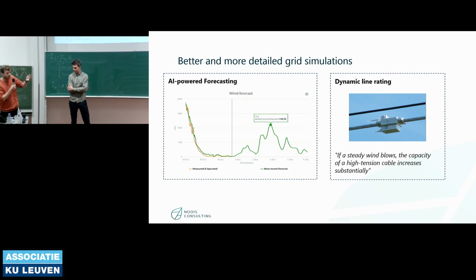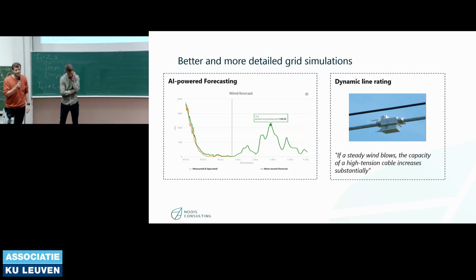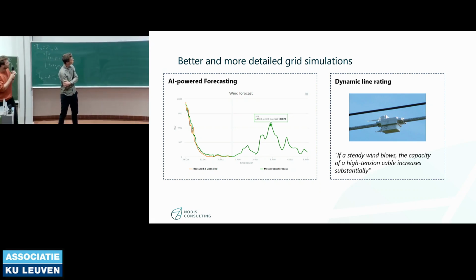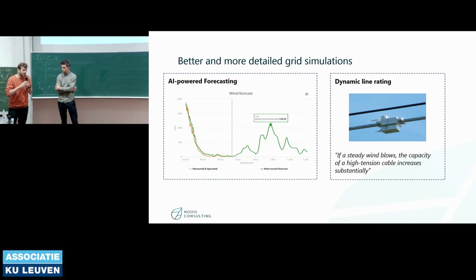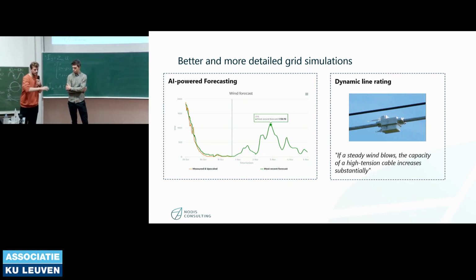Even further, the cables are actually not on the ground, they're in the air. So you have models that predict, okay, here it might be 17 degrees, but actually in the air at 100 meters or maybe 75, it's 15 degrees - that has an impact. And why does that matter? Because of dynamic limit management - one example is dynamic line rating, it's all thermal energy. So if it's colder, the better, your capacity increases, not only on the lines but also on your transformers and other grid elements.